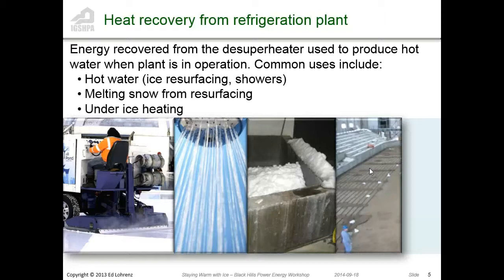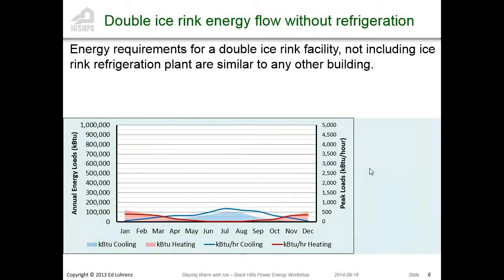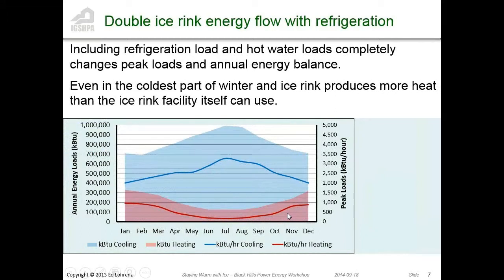We look at a typical, this is a double ice rink. Here's the heating requirements of a typical building like that. Once we add the refrigeration loads, look what happens to the cooling loads and the domestic hot water needed to flood the ice. They change quite a bit. Ice making is pretty energy intensive.